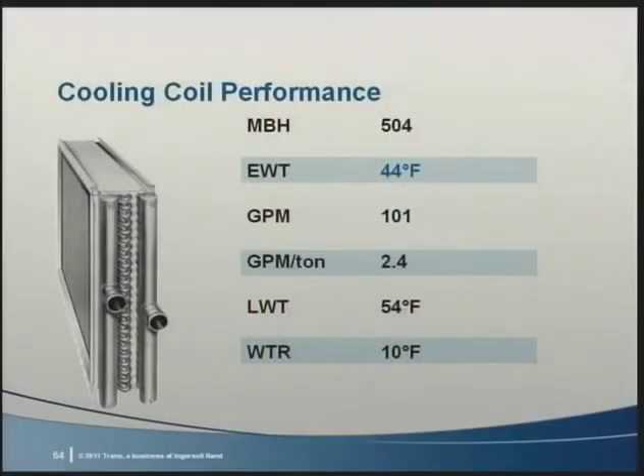This coil was originally selected to deliver 504 MBH or 42 tons. The entering water temperature is 44 and 101 GPM is required. Now note, this is the old high flow rate of 2.4 GPM per ton. The water leaves the coil at 54 degrees, giving a water temperature rise of 10 degrees. Now in this example, we want the same airside performance from the coil.